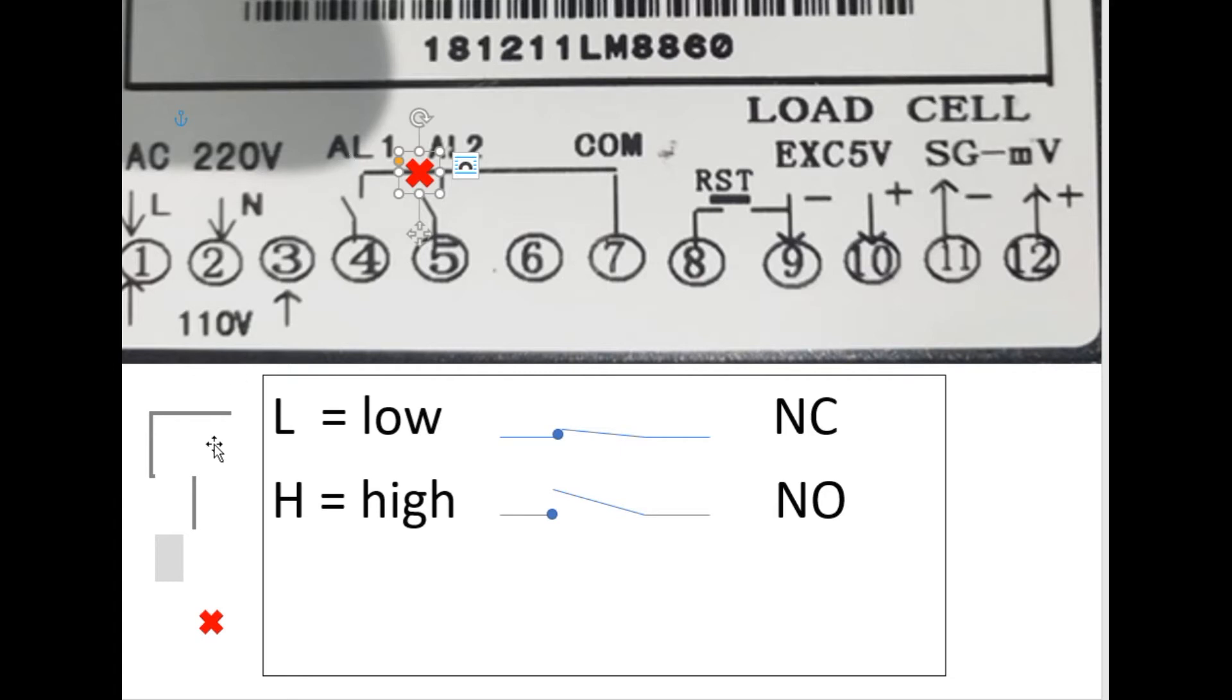I cut this one from here, so seven is not anymore connected to L1. So I have to create a common for L1. So I have run a wire from here to number three, and from number three from inside this one I cut it. So this one became now the common for L1 and seven became the common for L2, I mean alarm one and alarm two.